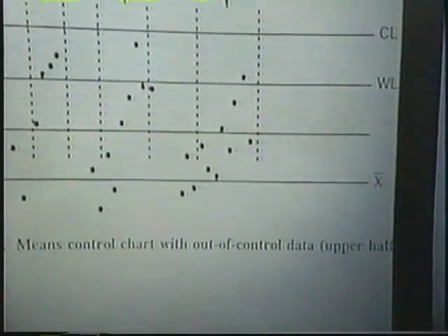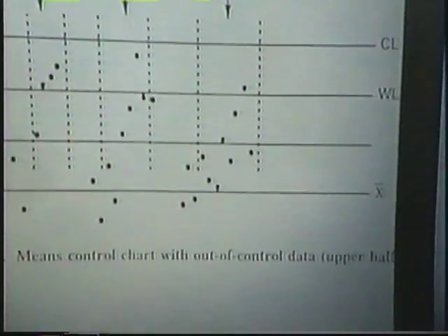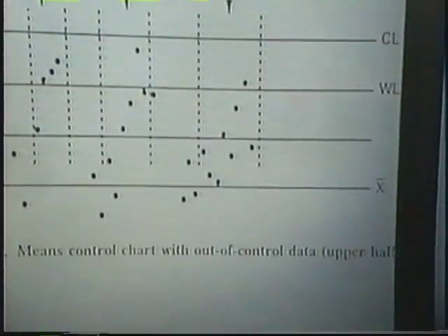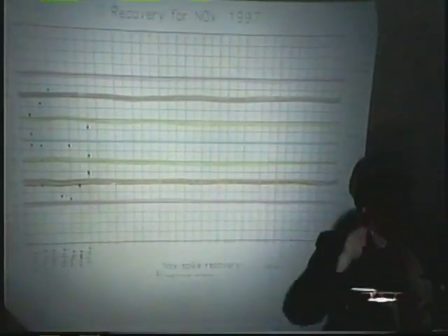The real value of this kind of thing, aside from guaranteeing the quality of the results that you give to your customer, the person that's using the data from this kind of measurement system, is that the analyst, using these kinds of indications of quality, should be able to spot a problem coming before it occurs because of this tendency away from the mean, this bias away from a normalized distribution. They should see that their system is starting to go out of control.